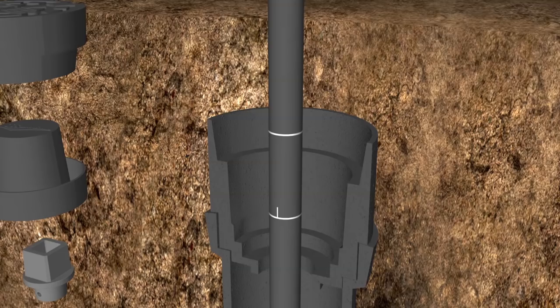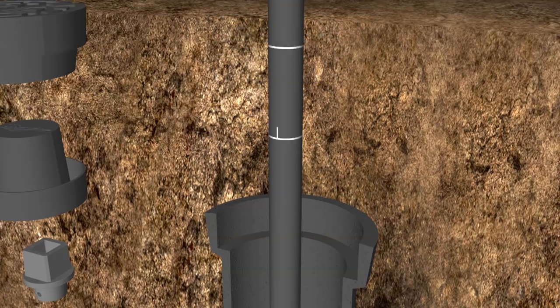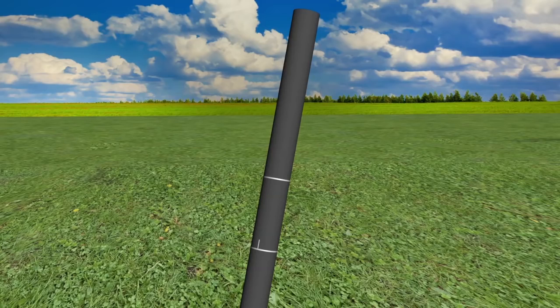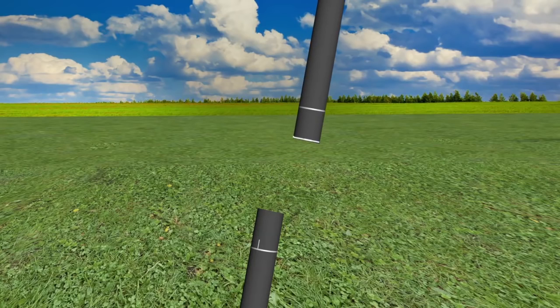Remove the position indicator, housing adapter, and the now marked extension stem. Measure 3 1⁄4 inch below the grade line and mark. This new mark is your cut line. Cut the extension stem at the cut line and deburr any sharp edges.